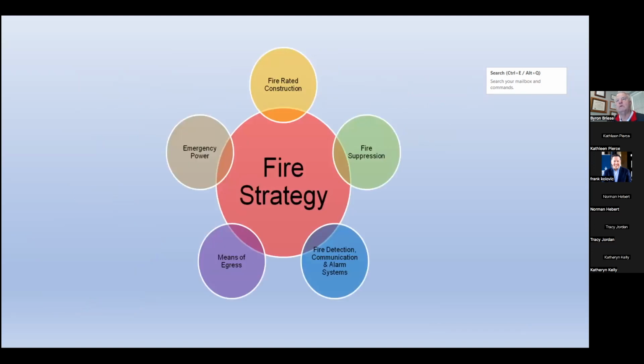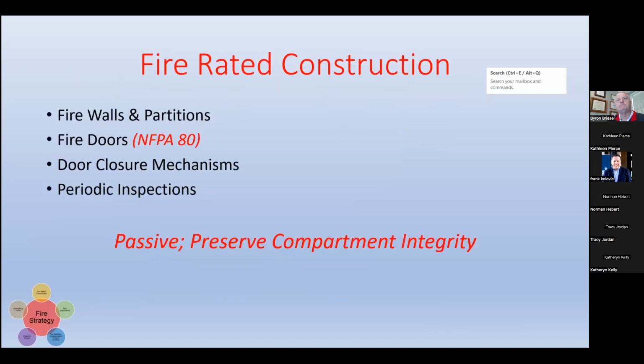See one more depiction of that. So our fire doors, fire walls, keeping good. They're passive, keep them in good condition. I have NFPA 80 noted next to fire doors. There is an often, if not 100% overlooked inspection obligation in there on an annual basis to at least do a minimal review and document it of your fire doors. And in legal cases, that one's popped up as a hole in a protective program, and it has caused people to have problems, but it's overlooked more than it's actually used.